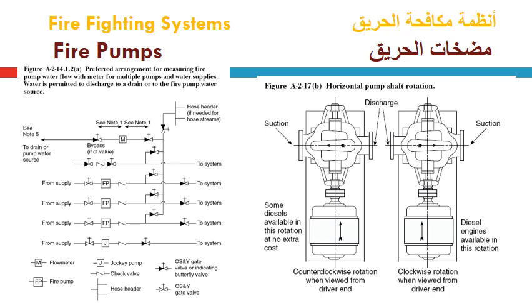During design and pump orientation inside the fire pump room, this direction of rotational motion should be considered, and the direction of the suction and discharge flanges should be adopted. The suction flange is recommended, or it must be, towards the suction tank, and the discharge is directed to the discharge header which provides fire water to the building served by this pumping system.